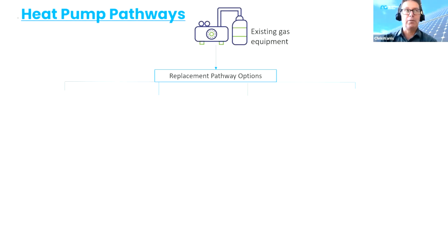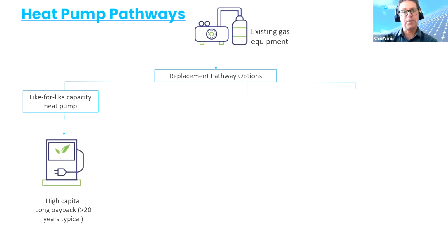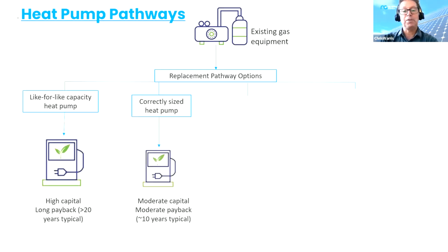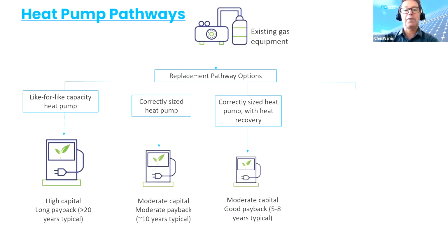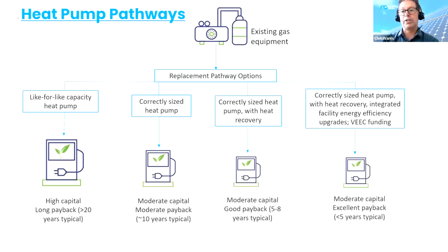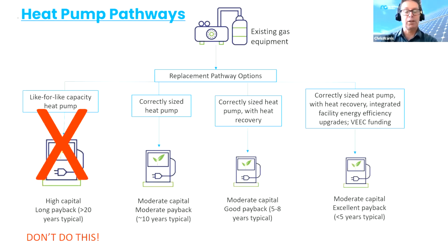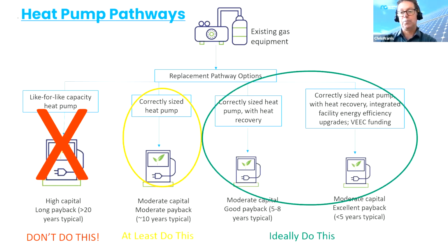But if you're looking to replace your gas boilers, you can do the like-for-like capacity replacement, which is going to be expensive, long payback. Much better to correctly size it. Use heat recovery if you can, and combine it with energy efficiency and get a really good result. So don't do the like-for-like replacement. If nothing else, just size it correctly. Even if you're just looking at the heat pump only, you'll get a decent payback. And then ideally do a more integrated design.